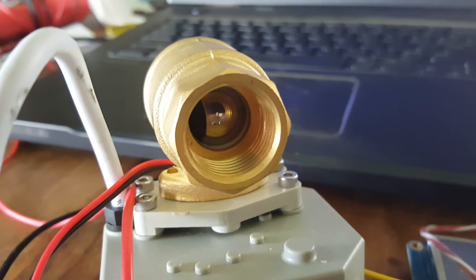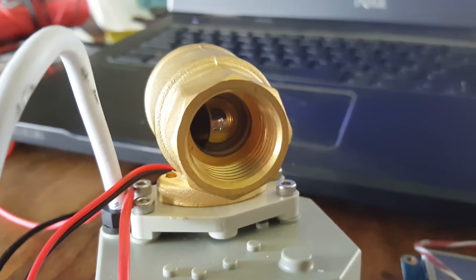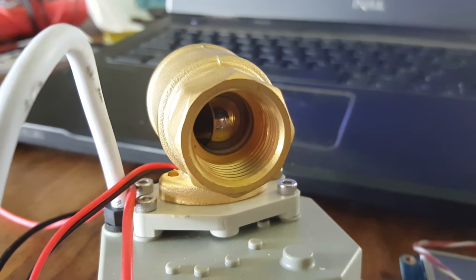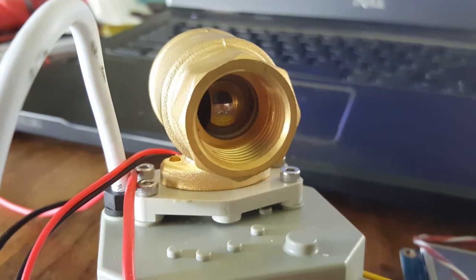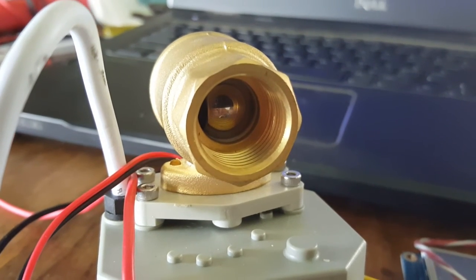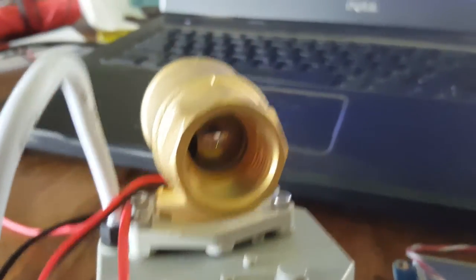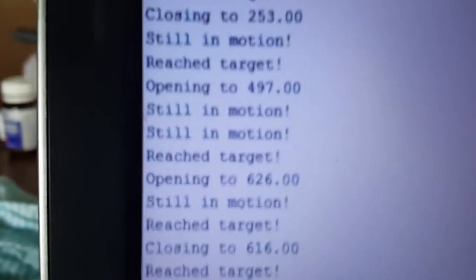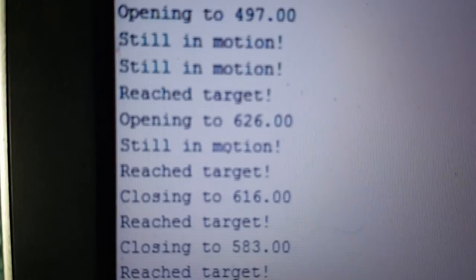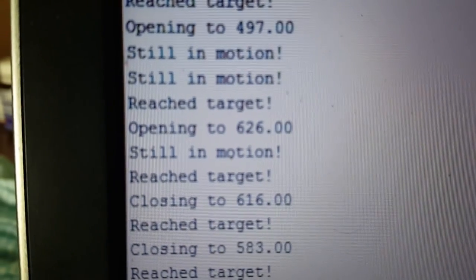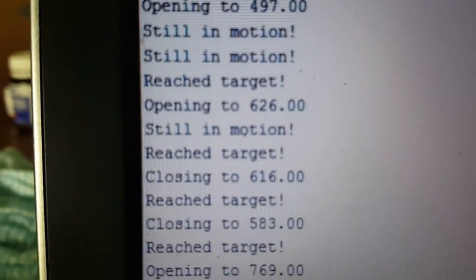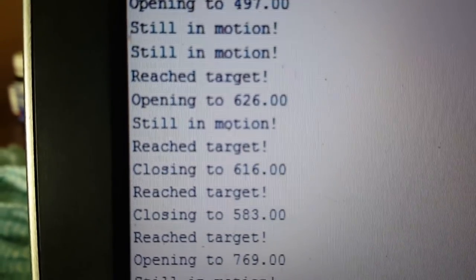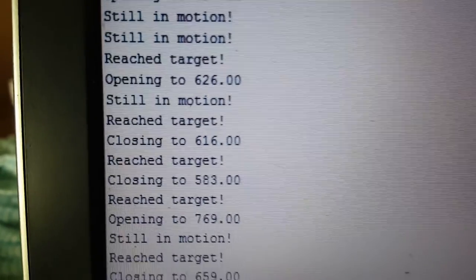So that's 10 adjustments per second. If the movement required is greater than what the valve can move in that 100 milliseconds, then what it does is says I'm still in motion and then waits until it's reached the target before it will take the next number generated by the random number generator.